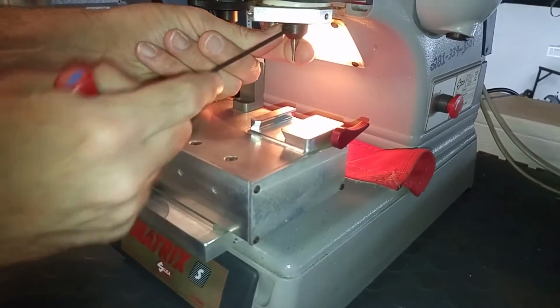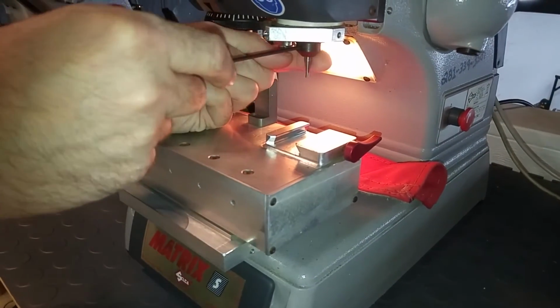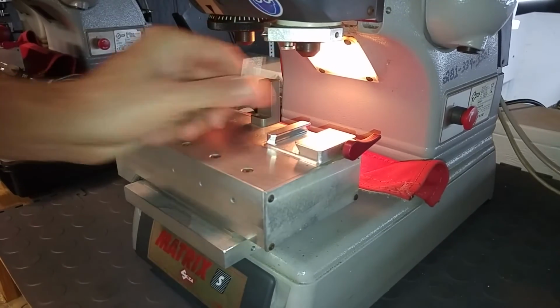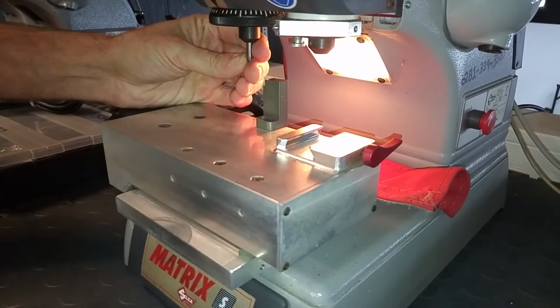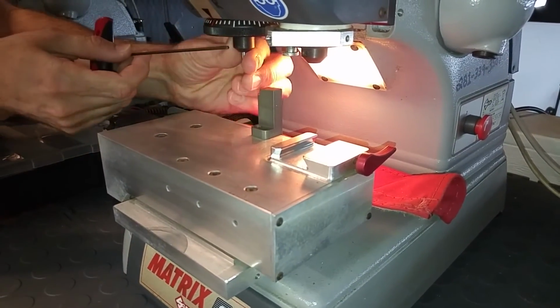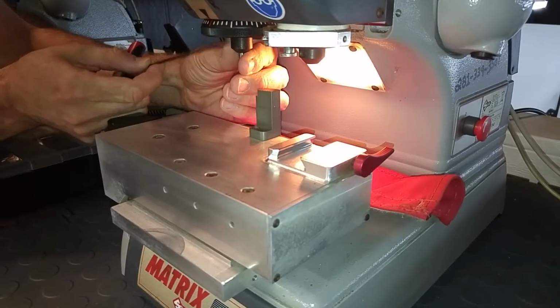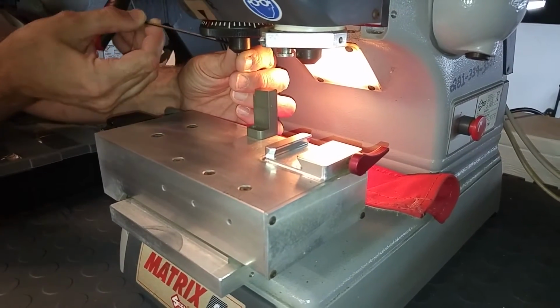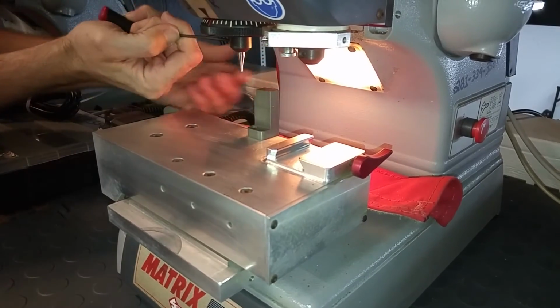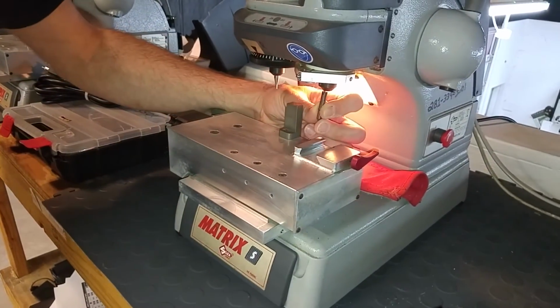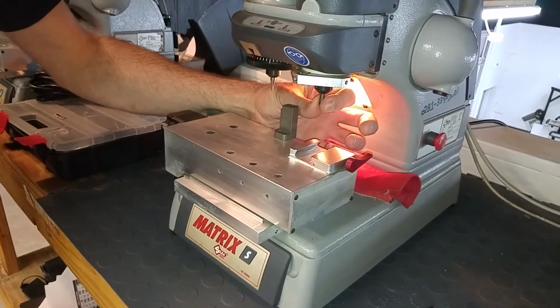Now we're doing the cutter height calibration. We're setting up for the calibration of cutter height, so we'll remove our stylus and place it back in its position on the left hand side. It doesn't really matter how high, we're going to be adjusting that momentarily. Just get it up in there a good distance. Now then take our cutter to 2.5 and place it in the right side until it stops on the retainer ring.